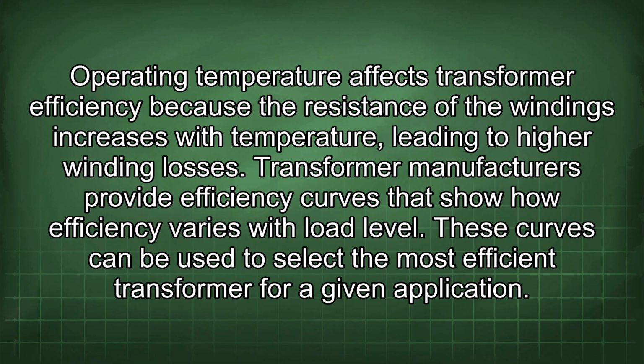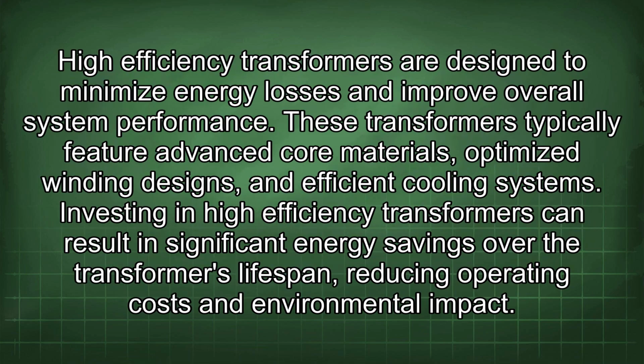Transformer manufacturers provide efficiency curves that show how efficiency varies with load level. These curves can be used to select the most efficient transformer for a given application. High-efficiency transformers are designed to minimize energy losses and improve overall system performance. These transformers typically feature advanced core materials, optimized winding designs, and efficient cooling systems. Investing in high-efficiency transformers can result in significant energy savings over the transformer's lifespan, reducing operating costs and environmental impact.